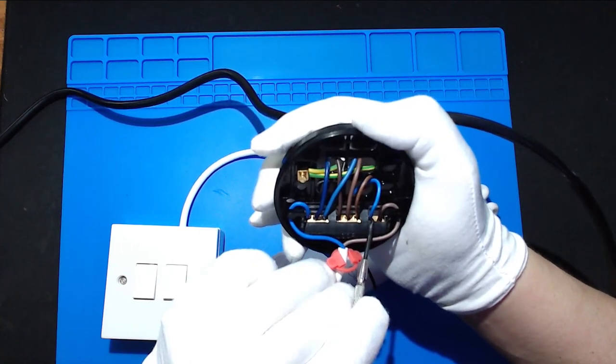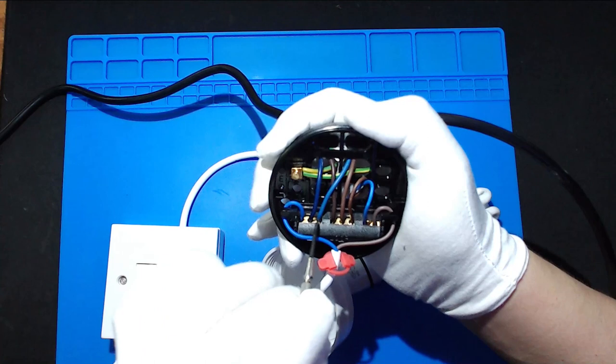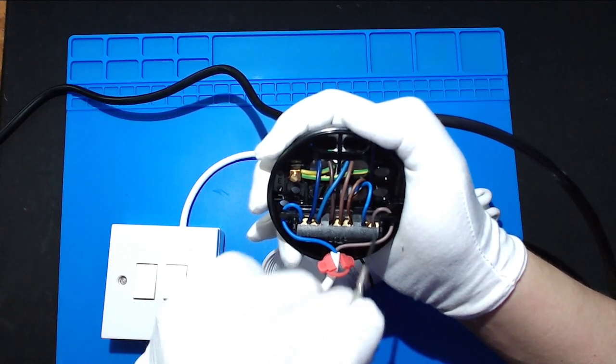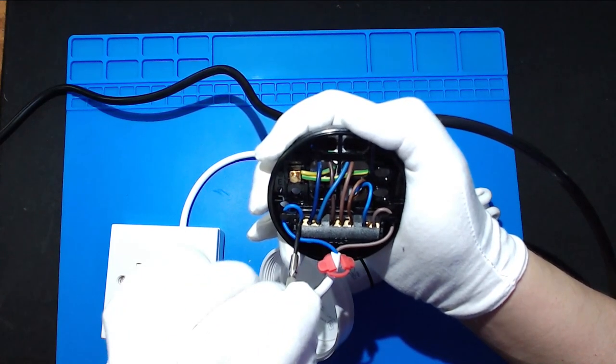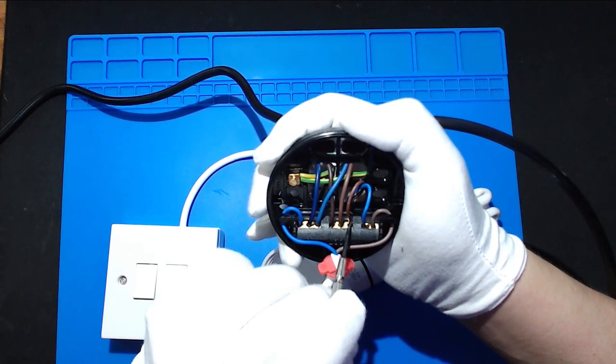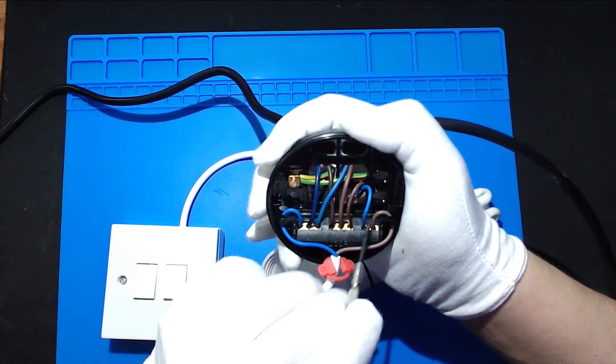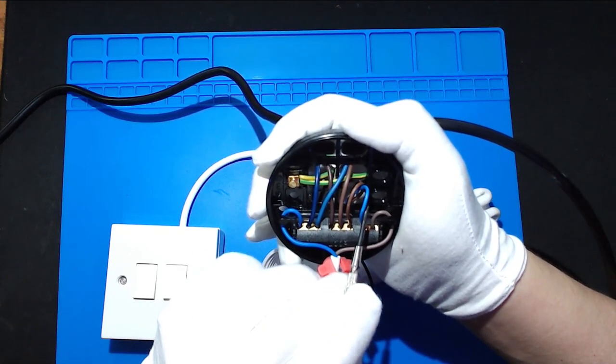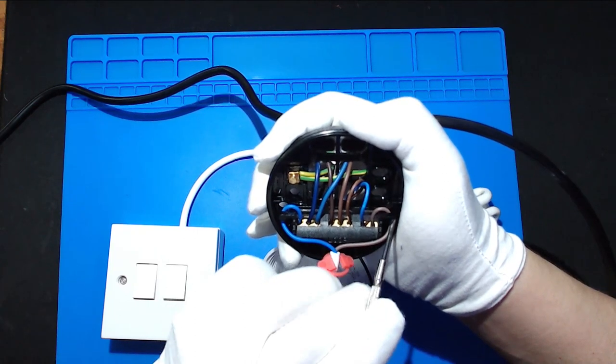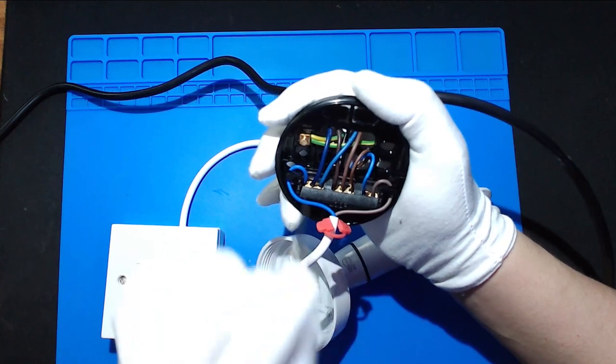This one is connected to your light. So you've got a three, a three and a two. So your three neutrals are all common. The three brown wires are all common in the three block there. And then you've got your switched live and your lamp coming out. What we want to do is we want to take all these wires out. Just leave the two light bulb ones.